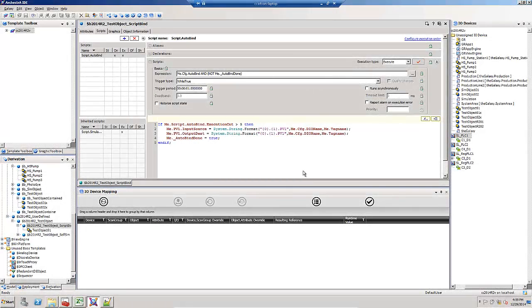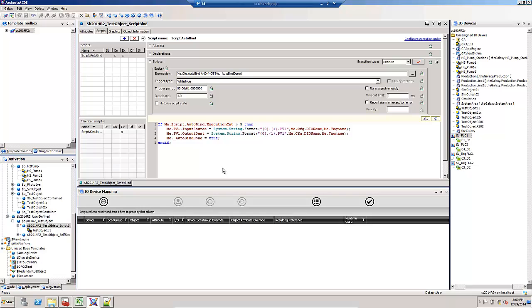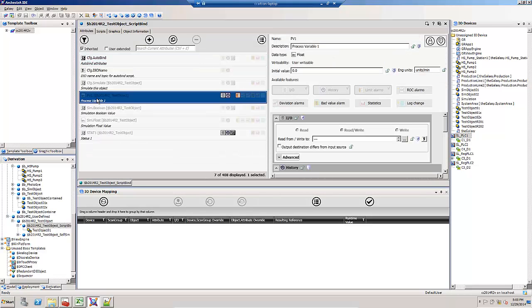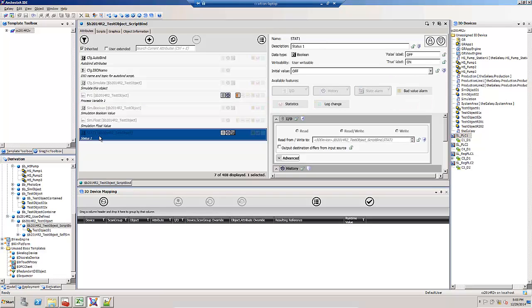What if I'm using scripted auto-binding? Maybe I've migrated a Galaxy from a previous version where I was using the base template library or I've written my own auto-binding scripts. Here's an example of a template with an auto-binding script for one of the attributes. I've got two attributes with IO extensions, one is the PV1 and the other is STAT1.